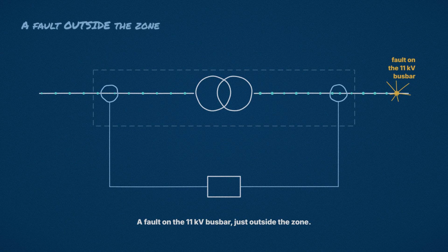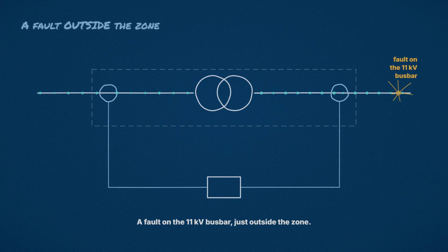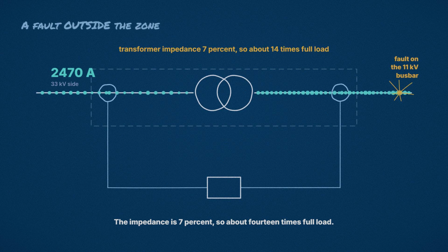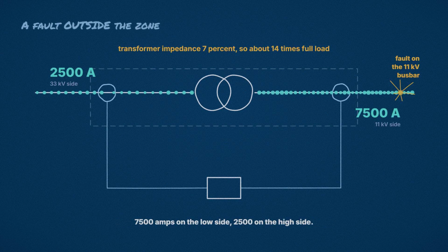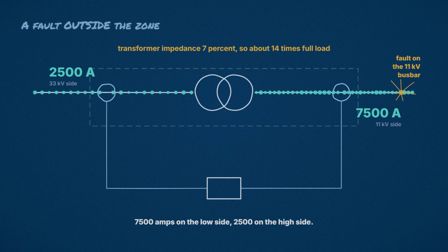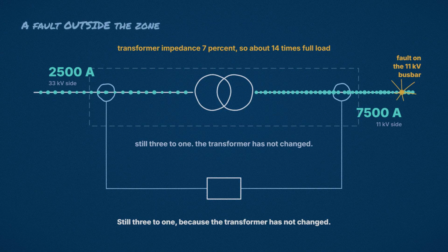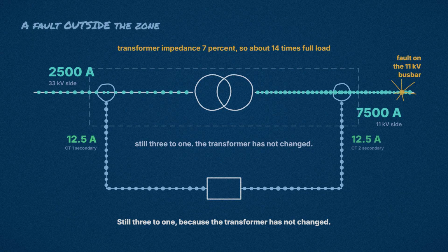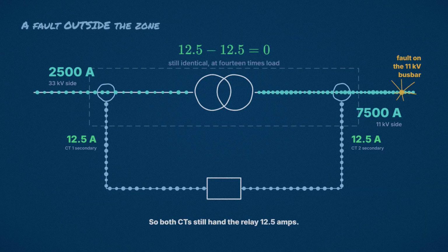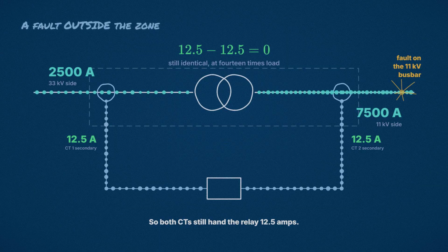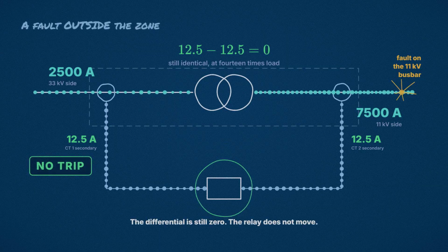Now a fault on the 11 kilovolt bus bar just outside the protected zone. The transformer impedance is 7%, so the fault current settles at about 14 times full load. That is 7,500 amps on the low voltage side and 2,500 amps on the high voltage side. Still 3:1 because the transformer itself has not changed. So both current transformers now hand the relay 12.5 amps. Still identical. The differential current is still 0, and the relay does not move.